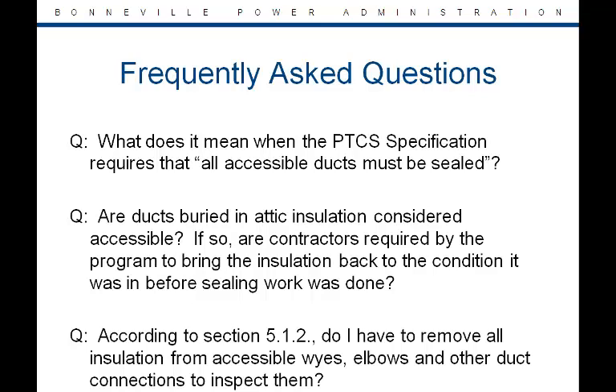What does it mean when the PTCS specification requires that all accessible ducts must be sealed? If a reasonable technician can reach the ducts in an unconditioned space, then the ducts must be sealed. The follow-up question to that has been, are ducts buried in attic insulation considered accessible? If so, are contractors required to bring the insulation back to the condition it was in before the sealing work was done? Ducts in attic insulation are considered accessible.